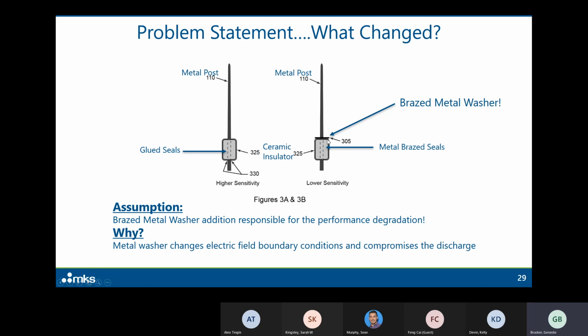And our basic assumption became that it was this additional washer that is typically thrown into feed-throughs that was causing the headaches for us. It's very common, right, in a brazed all metal feed-through to incorporate a little washer on top that is completely brazed onto the ceramic and onto the anode. And that is a big part of the vacuum hermetic seal, right, that these feed-throughs provide. So our assumption became that it was this brazed metal washer that was responsible for the performance degradation. Our explanation or root cause was that it was really affecting the boundary conditions of our electric fields, and it was compromising the discharge.